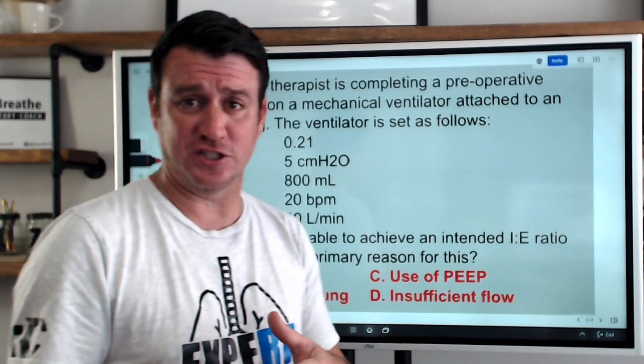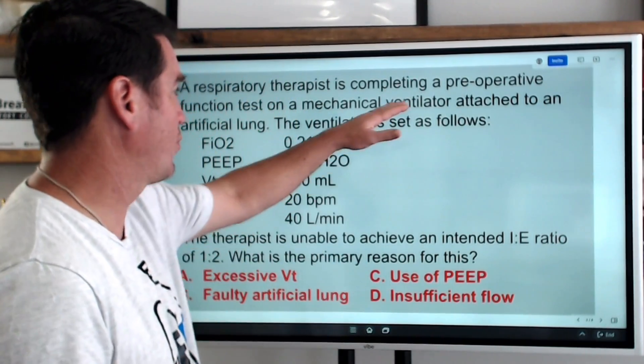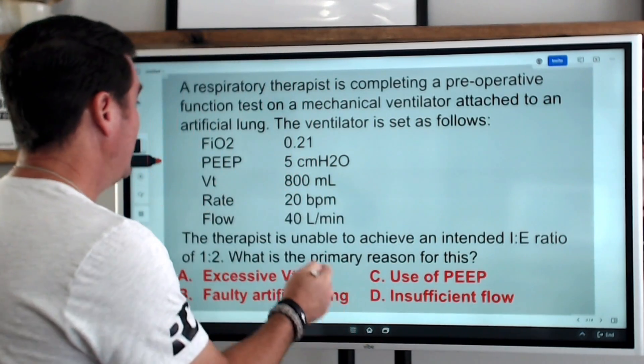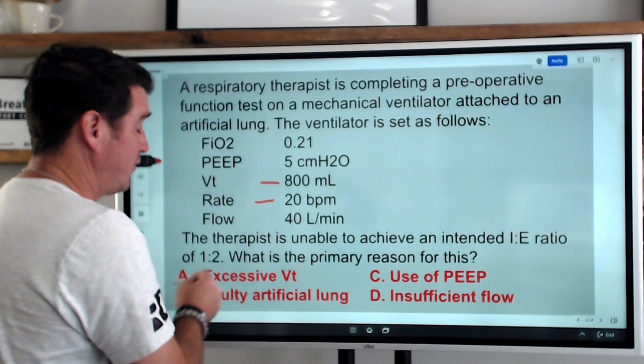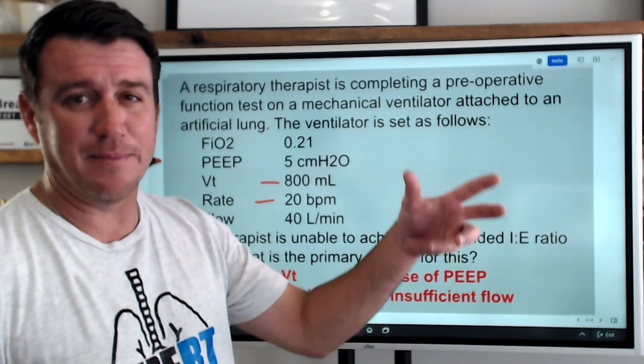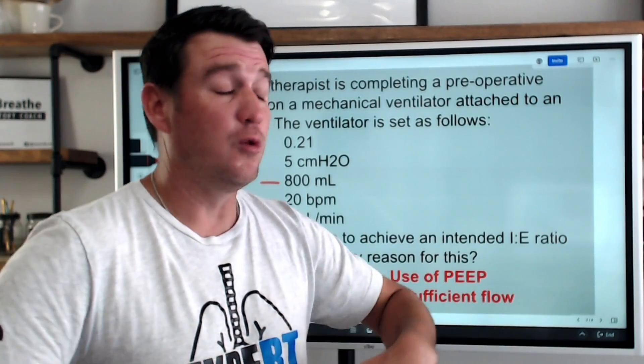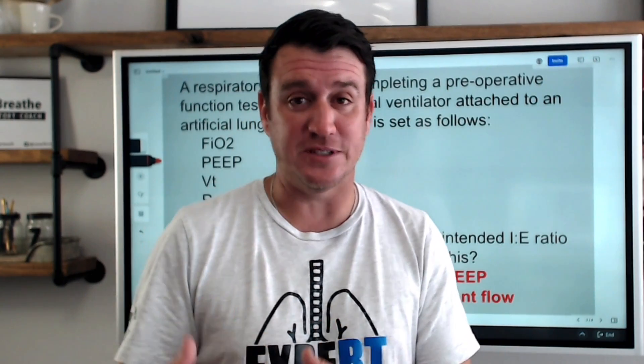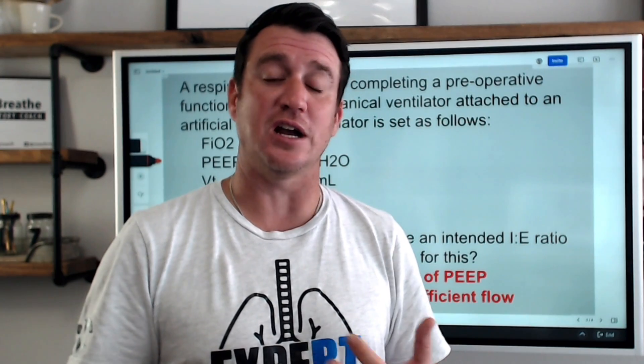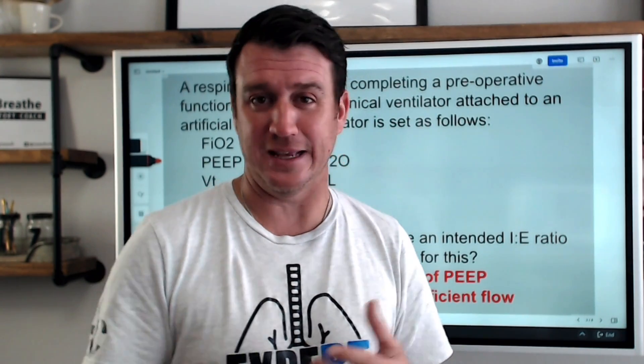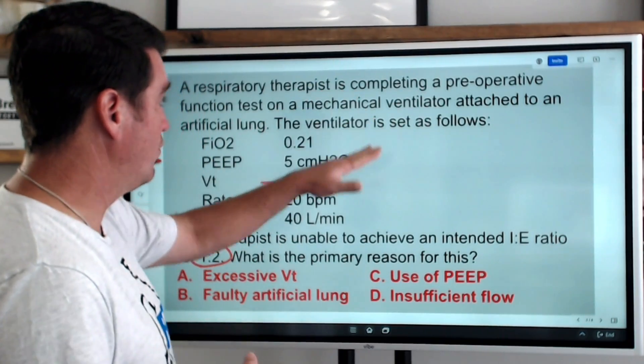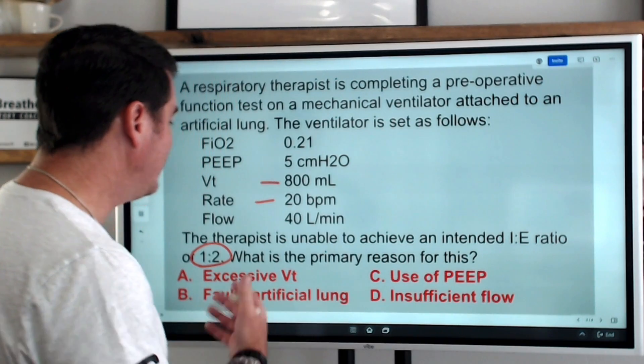When I look at this question, there's a couple things that jump out at me. First of all, I've never done a preoperative function test to test if the vent is going to give 800 mLs, rate of 20, and establish an I:E ratio of one to two. That sounds more like biomedical stuff to me but nonetheless, we do oftentimes perform system tests to make sure that the pressures are held, that there's no leaks, that the filters are not causing any type of flow impedance, and things like that. So we do perform preoperative tests. I just don't know if you've ever seen one or done one like this.